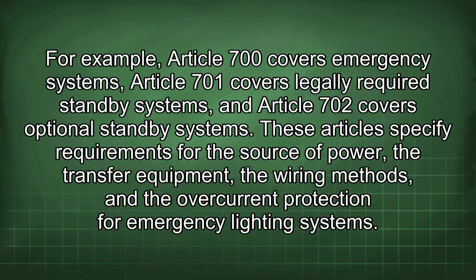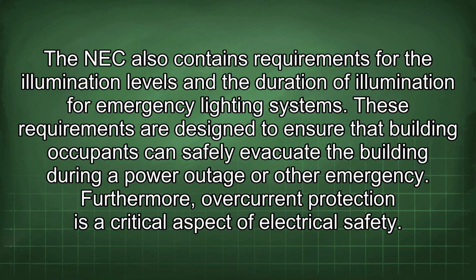For example, Article 700 covers emergency systems, Article 701 covers legally required standby systems, and Article 702 covers optional standby systems. These articles specify requirements for the source of power, the transfer equipment, the wiring methods, and the overcurrent protection for emergency lighting systems. The NEC also contains requirements for the illumination levels and the duration of illumination for emergency lighting systems. These requirements are designed to ensure that building occupants can safely evacuate the building during a power outage or other emergency.